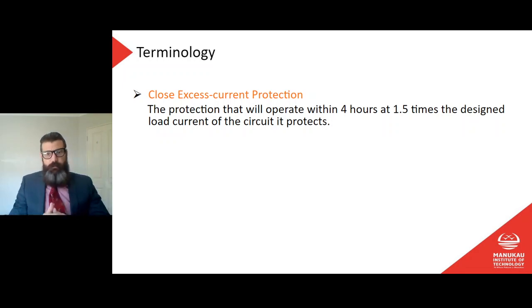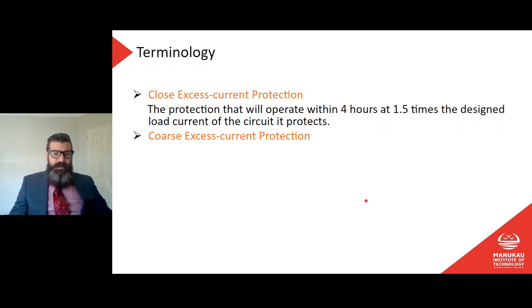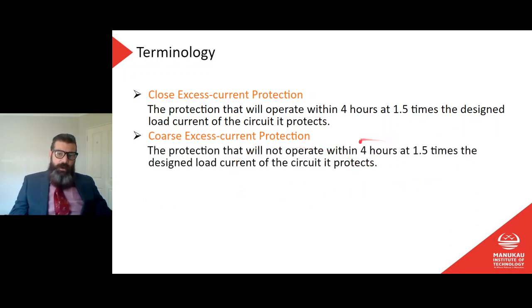So that's the higher level of current protection. That shows you that even at 1.5 times the rated current, so 30 amps on a 20 amp circuit breaker, it often will not trip. It could take up to 4 hours to trip. Coarse excess current protection does not operate within 4 hours. So it takes longer than 4 hours at 1.5 times the designed current. So again, for a 20 amp breaker or 20 amp fuse, if I put 30 amps through that, then the coarse protection is going to take more than 4 hours to trip. So that's the difference between close and coarse excess current protection. Just try your best to memorize those definitions.